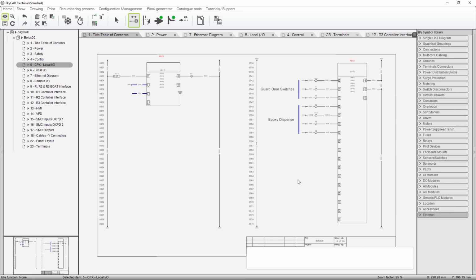Now the guard door switches, these are not safety inputs. The guard door switches each have 2 channels that go to the CR30 programmable safety relay. These are aux contacts, auxiliary contacts, that you can use to see whether a guard door is closed or not closed, and you can use that for your HMI display. Now you could have done the same thing through Ethernet, because our CR30, we're using Ethernet, so I could have accessed some of that information and figured out a way to do it on the HMI anyway. But hey, if the guard door switches have aux contacts, let's use them.